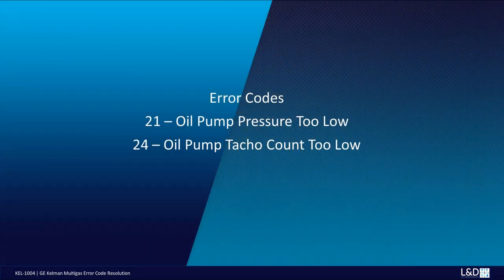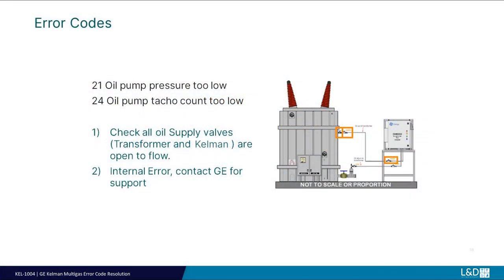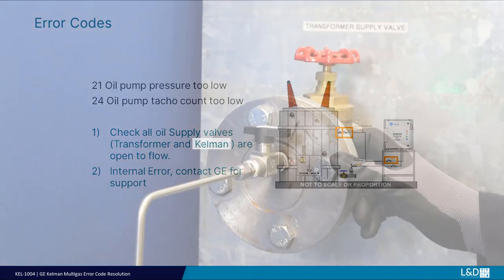Error code 21: Oil pump pressure too low, or error code 24: Oil pump tacho count too low. Check all transformer and Kelman oil supply valves are fully open to flow.